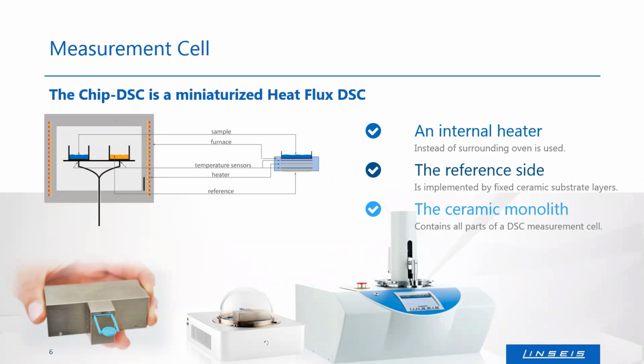We've changed the layout to a vertical way. At the top is still our crucible with the sample inside, and below you will find the temperature sensor for the sample. In the middle of our sensor, you will find the heater, so there's no surrounding oven anymore. Below that, you will find the temperature sensor for the reference, and at the bottom, the fixed reference. Everything is inside of one ceramic monolith.